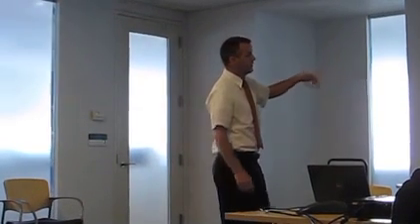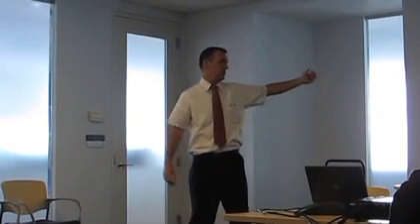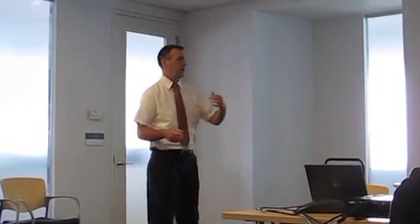So when you are looking at transfer switches, you have the size of the transfer switch for the load requirements. You know, how big does that transfer switch have to be to meet the electrical load duty, fault duties, things like that. When you're controlling and monitoring it, or there are certain control and monitoring aspects of it, again, auto or manual, do I have open or closed transition?